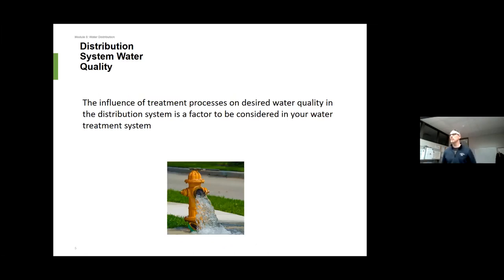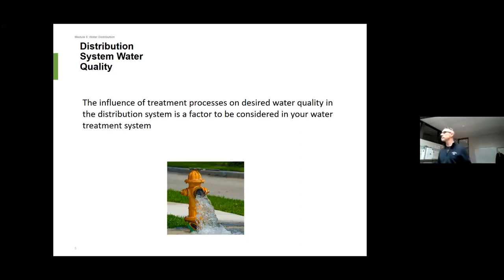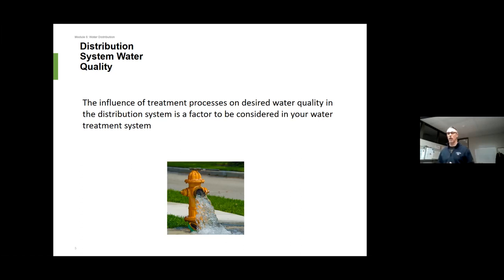The influence of the treatment process on desired water quality is a big factor. All the treatment processes we talked about — we have to get that water ready to go through the pipe network and into our storage reservoirs. If that water is too aggressive, meaning the pH is too low or it doesn't have enough minerals, it will actually eat some of the pipe network. If it has too many minerals or the pH is too high, we might have issues with pipes crusting up or incrustation in the pipe, which blocks up the pipe. We also have to make sure the pressures are correct so we're not doing damage to our pipe network.